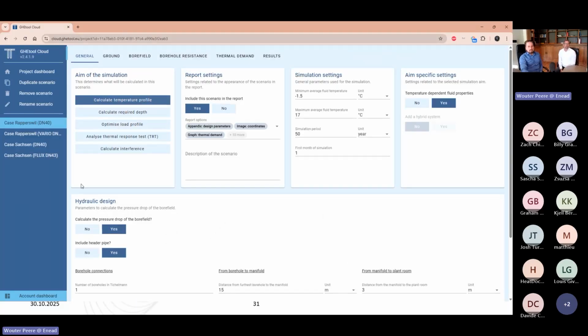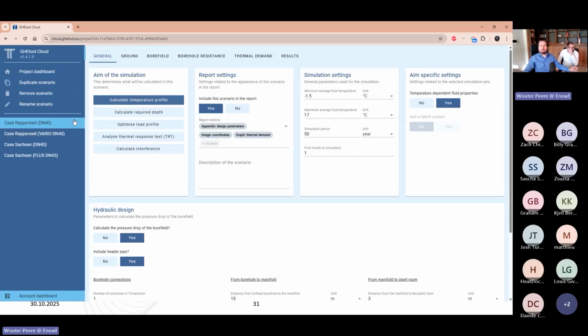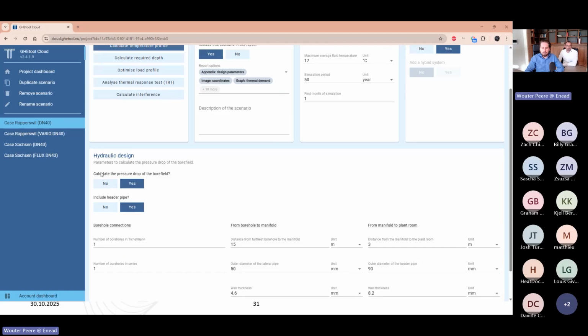Perfect. So let us go ahead and see how we can translate these parameters into our software. Without going too much into detail, we created a couple of scenarios. The first case is in Rapperswil. We will first take a look at the traditional DN40 probe and then compare it to a VARIO. So what we did is we calculated the temperature profile with a minimum and a maximum average fluid temperature. And we also calculated the pressure drop. All the pipes were connected in parallel with certain distances from the borehole to the manifold and to the plant room.